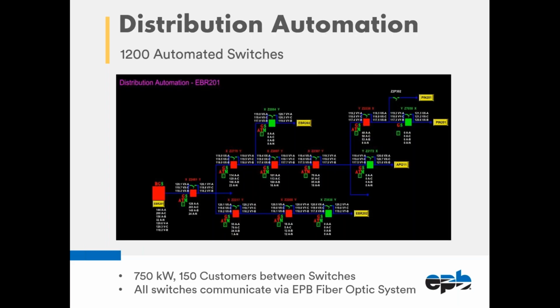Back in 2010, 11, and 12, EPB installed about 1,200 automated switches on our 12 kV distribution system. This is a schematic of a typical feeder: the substation breaker is on the far left side, each of the red boxes are normally closed switches, and each of the green squares are normally open switches that tie to other feeders.